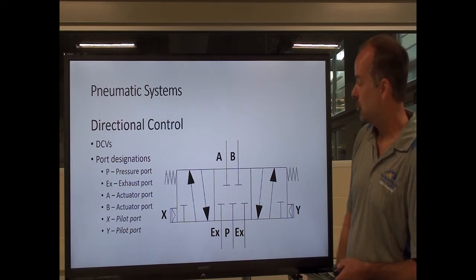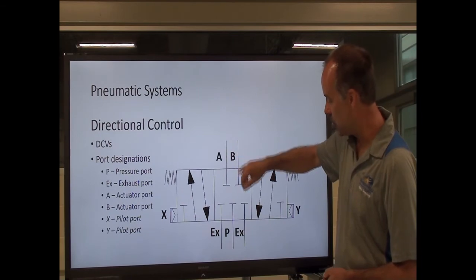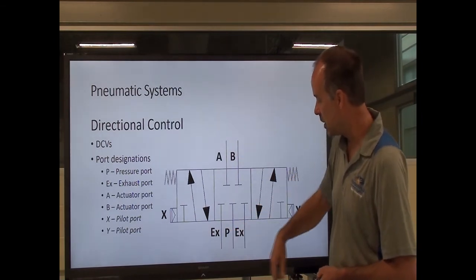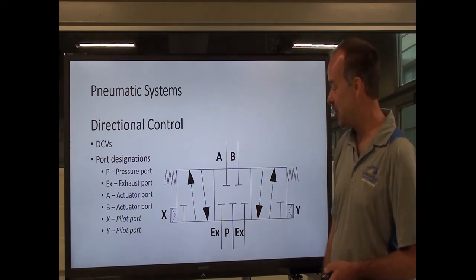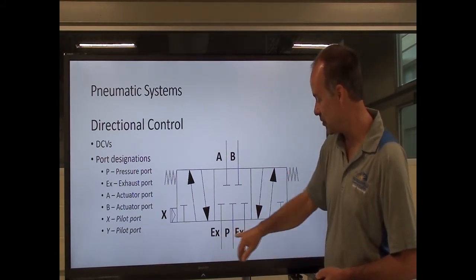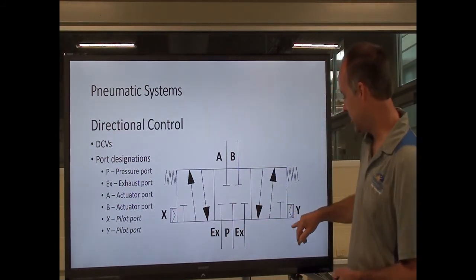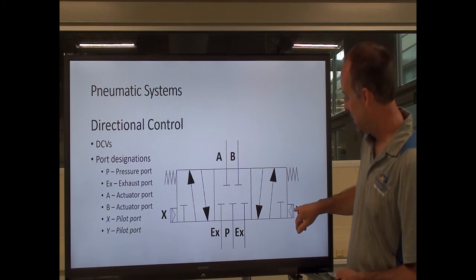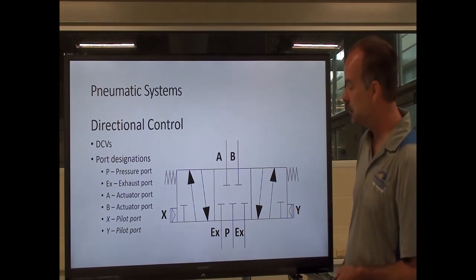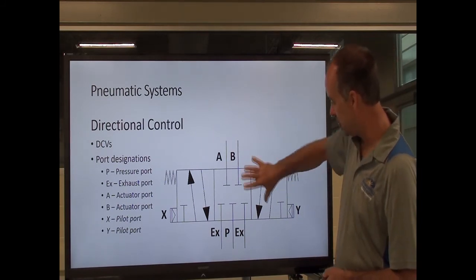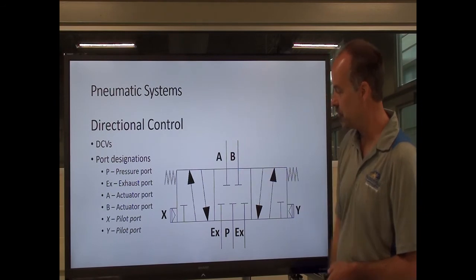For directional control symbols: one difference with pneumatic DCVs is that you still have A and B ports and a pressure port, but instead of tank ports, you don't have a reservoir to send the air back to — it's just exhausted to atmosphere. So now you have exhaust ports. You can also have pilot ports; notice that these triangles are not colored in, telling me this is a pneumatic pilot. But it's pretty much the same nomenclature with just a few minor differences.